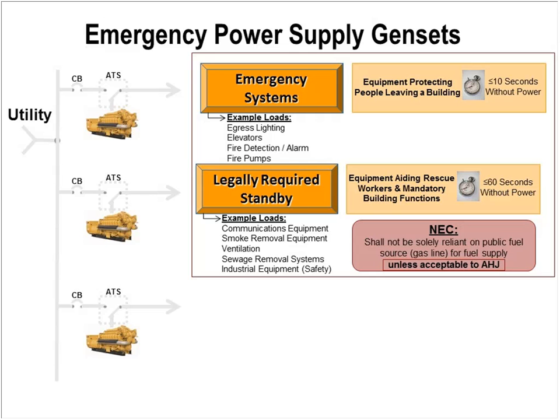For example, during Hurricane Katrina, there were hospitals in New Orleans—5 of them—that had CHP systems. When diesel fuel was not available to those generator sets, we found that the gas, even though the pipes were underwater, was still available to the generator sets there, and so they simply moved the emergency loads from the diesel units to the gas units.